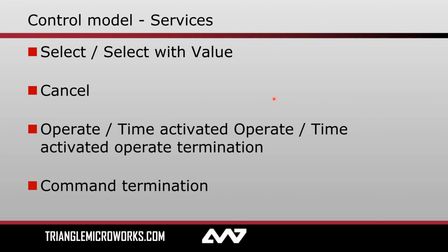So these are the buttons you can push, so to speak, in a tool like Test Suite Pro, or even in a SCADA tool or HMI, although they may be abstracted away slightly. But select and select with value, I've already spoken about that. Cancel. Once I have selected a specific control and I have the authority to operate it, I can then cancel that, giving that up. And then finally operate, and a couple variants on operate, which allow me to actually do the task that I'm trying to do, issue the control. All of these first 3 come from the client, whereas command termination is a service used exclusively by the server to let me know either I've timed out with my select, or the control was completed or not completed.